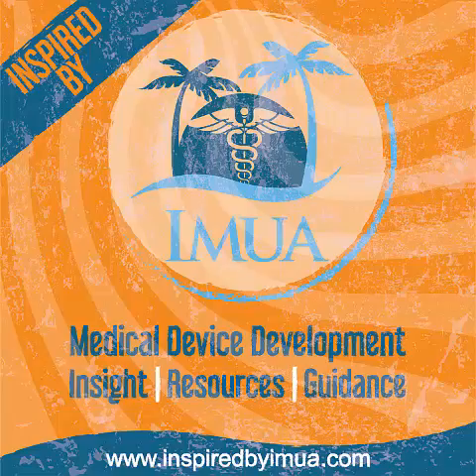There is an ASTM test method. ASTM is a society that creates standardized test methods for anyone to utilize. So ASTM has a test method around accelerated aging. It's widely used in medical device for packaging. It's a thermodynamic principle, and you can apply it really to anything where you want to accelerate time, basically.